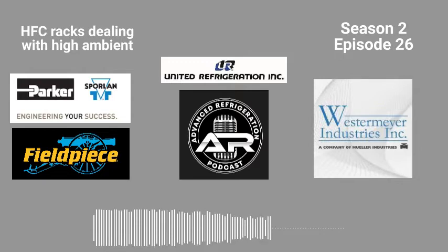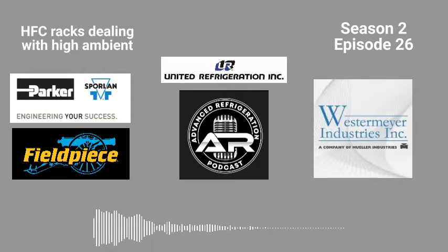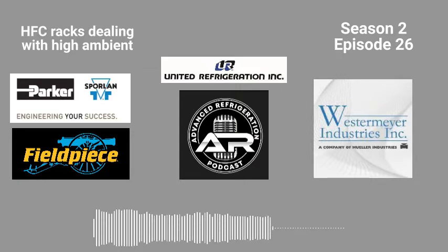That being said, if it's not doing that at that point, you're starting to look into all this other stuff that might be causing it to run higher than what it should. Usually it's the condenser's blocked. Usually it's a fan out. 85% of the time, it's usually because it's impacted.